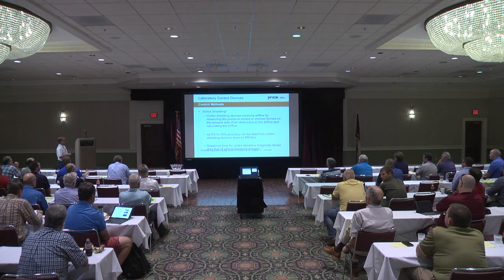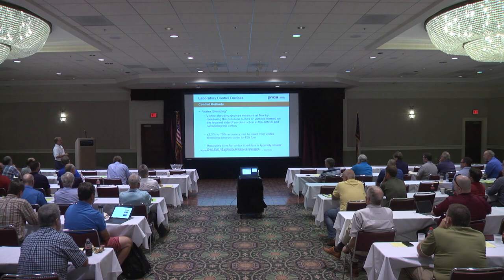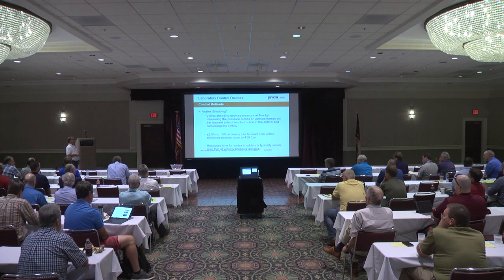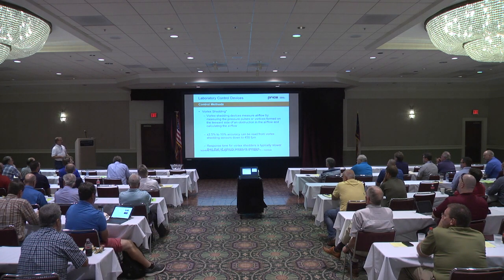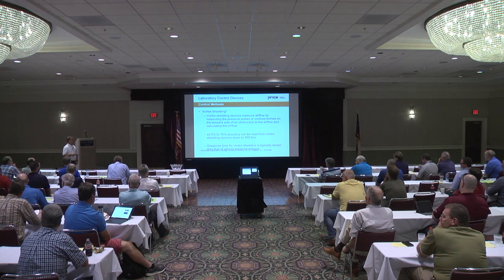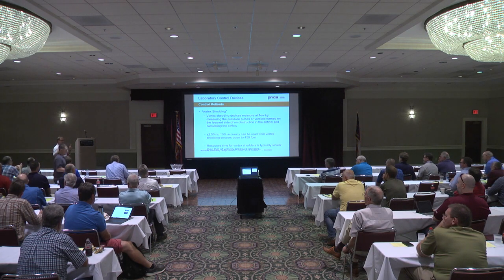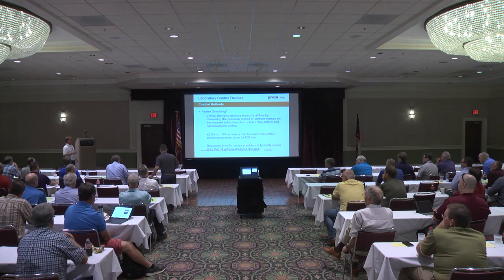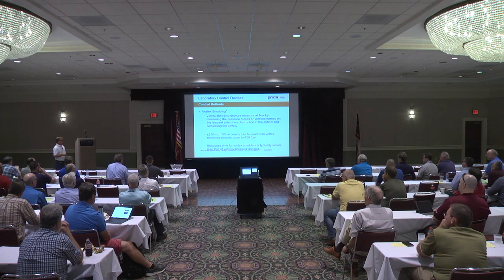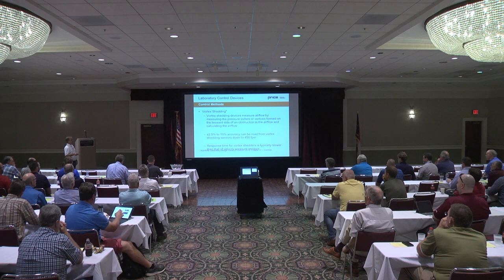Vortex shedding has become a popular way for one manufacturer to do airflow control. I don't know if you've had the chance to work with any of these devices, but it measures airflow using the pressure pulses or vortices formed on the leeward side of the airflow device. So it's controlling airflow with basically two different dampers, through vortices on each side of the device with nothing in the center. Actually, these are somewhere in the 2.5 to 10% range, with shedding sensors down to 450 feet per minute, sorry.